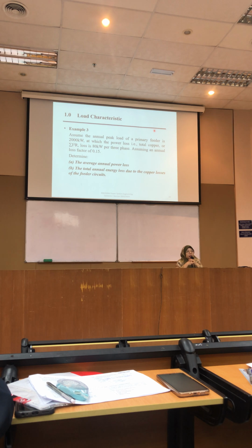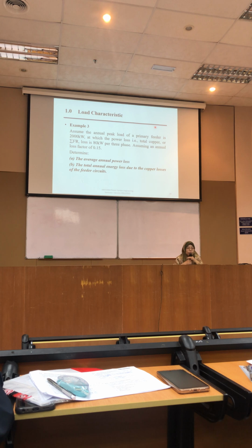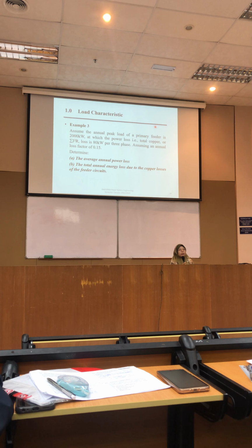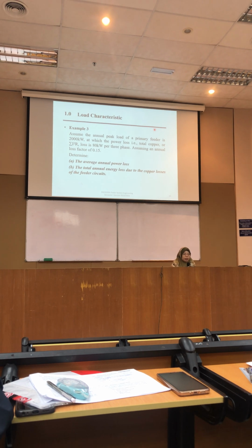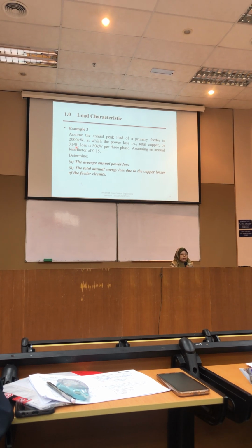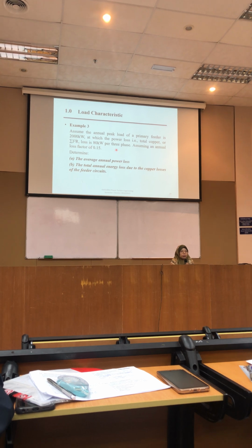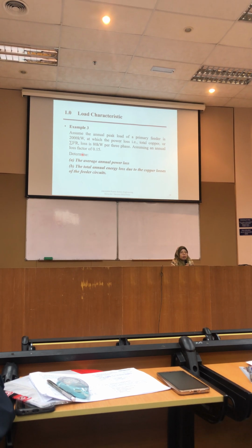You have studied this, right? ACSR, aluminium conductor steel reinforced, is for the transmission line. For cable, we use copper as well for distribution cable. So copper has been used as a cable, so that we can calculate the loss by using I square times R. The loss is 80 kilowatt per 3 phase, and the annual loss factor is 0.15.